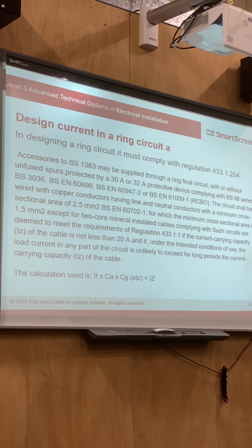Okay, but that's lazy, isn't it? To just go to table 54.7 and go, do you know what? I could install the same size earthing conductor and I'll be happy with that. Okay, that's lazy, isn't it? All right, who wants to do that tonight? Or shall we go for a smaller size cable and see how it works out? I'd say you'd learn more from seeing how it works out.